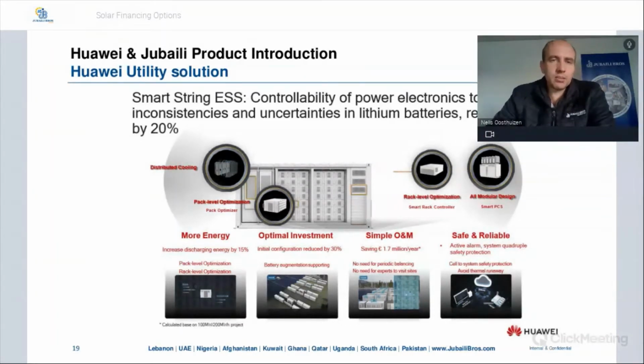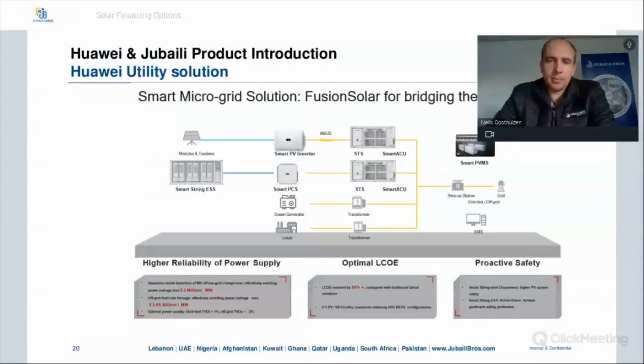So this next slide is focusing more on the battery system. It says the Smart String ESS, controllability of power electronics to resolve inconsistencies and uncertainties in lithium batteries, reducing your LCOS by 20%. So this 2 megawatt hour container system is made up of different battery packs, and each rack is individually controlled. It's a modular design, so if you have a problem with one specific battery module, you can just pull out that specific battery module and replace it. So by utilizing the smart battery system, you're simplifying your operation and maintenance, and that's also saving you time and money.